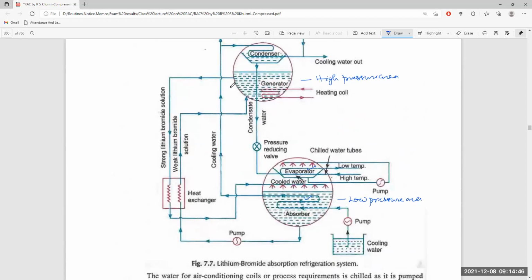It is this strong solution comes here. It is sprayed in the heat exchanger, then goes to the heat exchanger here, where the heat is being extended to the liquid solution, which again goes back to the generator, and this solution comes back here, and it is being sprayed here over the lithium bromide solution.